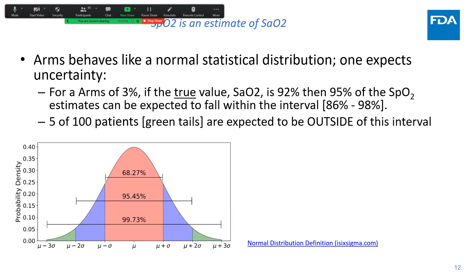And I just want to talk a little bit about statistics. Did this go backwards? Yeah, so this is the formula for root mean square error. We don't have to talk about that. But we know that these devices give an estimate. What that means is that for a given saturation value as measured by a co-oximeter, a pulse oximeter will have uncertainty. It could be plus or minus one standard deviation, which might be plus or minus 2 or 3, or plus or minus 2 standard deviations, depending on how you want to look at this. People say, well, why don't you just put the confidence interval on the front dial of the oximeter? Then you'll know that if it reads 92, it's 92 plus or minus 3. Well, the problem with that is it doesn't tell you what the accuracy is, what the underlying SaO2 value is.